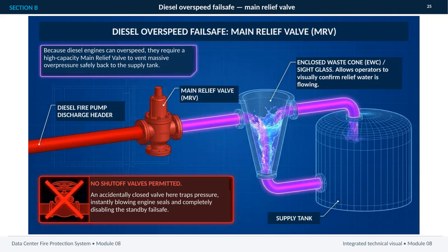This slide focuses on the diesel fire pump's overspeed failsafe, centered on the main relief valve, or MRV. Because a diesel engine can overspeed, it may generate a dangerous level of pressure very quickly. The MRV provides a high-capacity path for that overpressure, directing relief water from the discharge header back to the supply tank. The enclosed waste cone, together with its sight glass, gives operators a direct visual check that water is actually flowing through the relief system. That visual confirmation is important because it verifies the valve and discharge path are functioning when protection is needed.